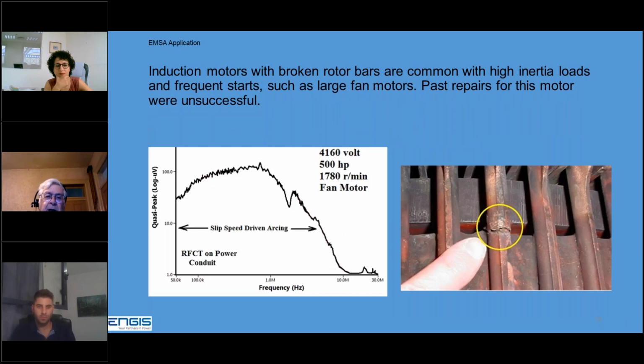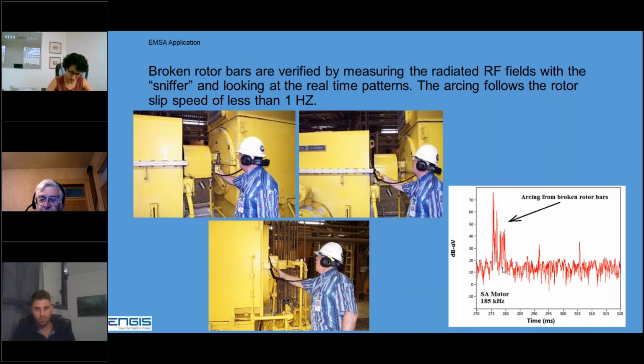Induction motors often will develop broken rotor bars if it's a very high inertia load and there are many starts, such as a large fan. This one in Wyoming had been repaired in the past, but with the first test, we could see from this pattern that it developed cracked bars again. And here's a picture of a cracked rotor bar on a machine. This pattern is very unique. The arcing happens at a very low frequency of less than 1 hertz. It's the slip speed of the rotor.